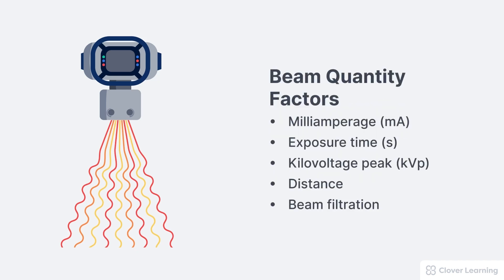The x-ray beam quantity is influenced by several factors, including the milliamperage (MA), exposure time, KVP, distance — specifically the distance from the radiation source to the point of measurement — and filtration. Changes to these variables have very predictable and measurable effects on the quantity or intensity of the x-ray beam.